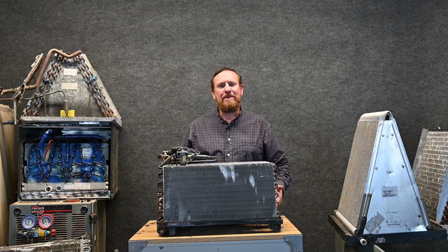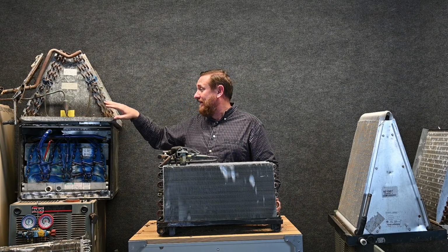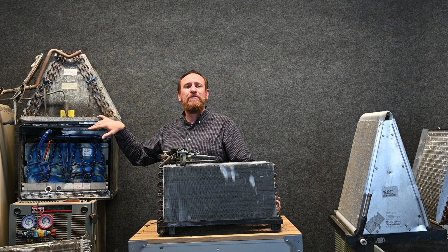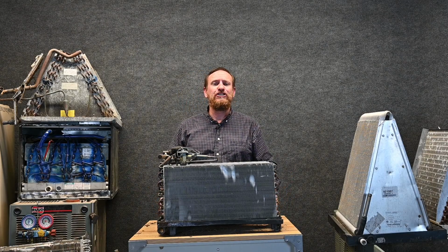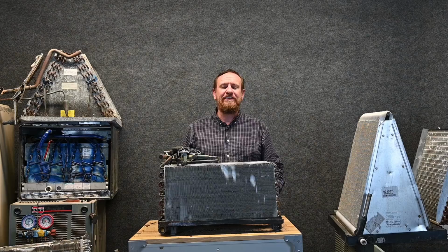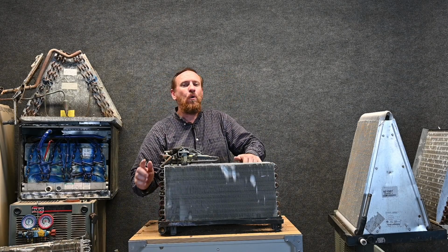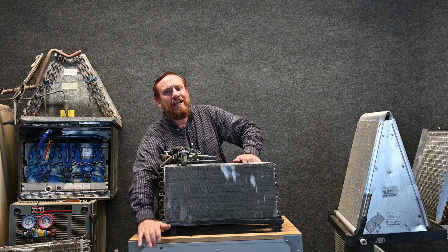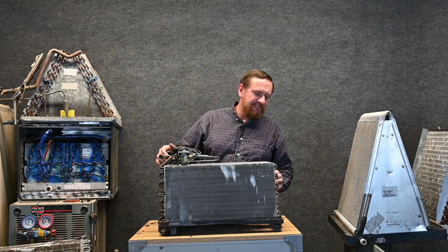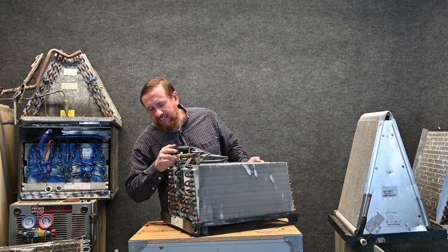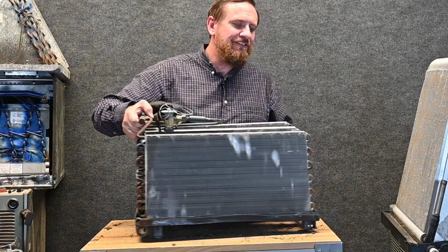This condensate drain pan is made out of plastic, where this condensate drain pan is made out of metal. In the old days, when it rusted out you could get a new one rebuilt. Ideally nowadays, the plastic or composite pans should never wear out. They should outlast the system, as long as the technician doesn't over tighten these threads, or somebody leans and applies pressure on that drain line and it snaps these drain pans. These evaporator coils are notorious for leaking right where the distribution tube goes into the evaporator coil. And these are very thin.